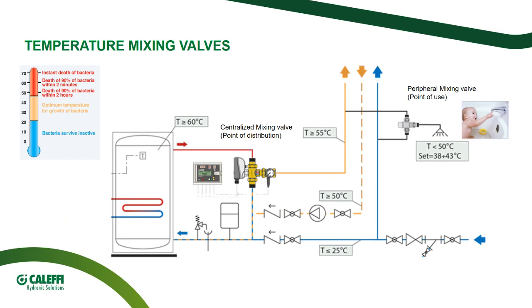Temperature mixing valves are control valves in order to control the temperature downstream to them. So this can be the typical schematic of a medium-big system. We can already identify different devices in different positions, so we can identify some mixing valve at the point of distribution, so close to the hot water storage or to the hot water generator, but we also can identify peripheral devices, peripheral mixing valve that we can define mixing valve at the point of use. Despite their operation might look similar, their features are completely different, and also some technical standards that they have to comply with. This is the typical trend of a hot water temperature throughout a medium-big system.